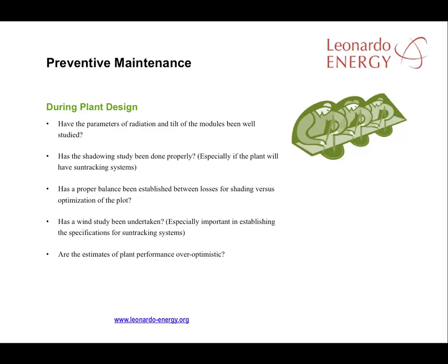For sites using sun trackers, the shading study is an important determinant of plant performance and it should be organised alongside a wind study. Third, the salinity and humidity of the local atmosphere need to be taken into account as that can influence the life of the selected fixings and support structures.